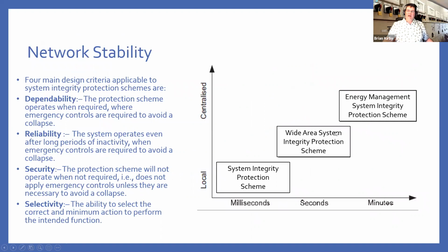Network stability sits in this sort of middle ground. You've got your traditional protection schemes, which are very localized and operate in the millisecond arena. And you've got your energy management systems, which are largely centralized, but operate in the terms of minutes. And you now have this middle ground, wide area system integrity, which is faster than your energy management systems, but not as fast as your local protection. And what they're doing is they're monitoring your network and trying to maintain stable power flows. But all of the constraints of your local protection, dependability, reliability, security, and selectivity still exist for this middle ground.